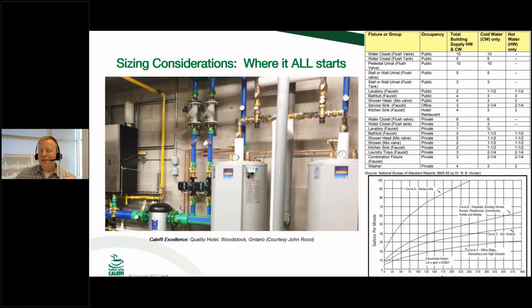Now, the next one that comes into play a lot, and I do mean a lot, is sizing. Oh my gosh, if I had a nickel for every time somebody sized a mixing valve based on pipe size, I'd be a millionaire and I could retire and I would share my wealth with all of you, okay? But that's not the case. I don't get a nickel for every time. I just get a phone call every time that the mixing valve is not sized properly.